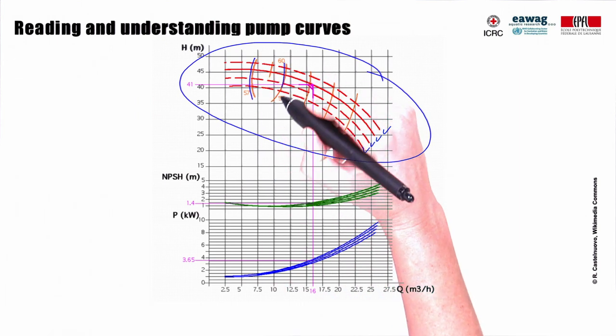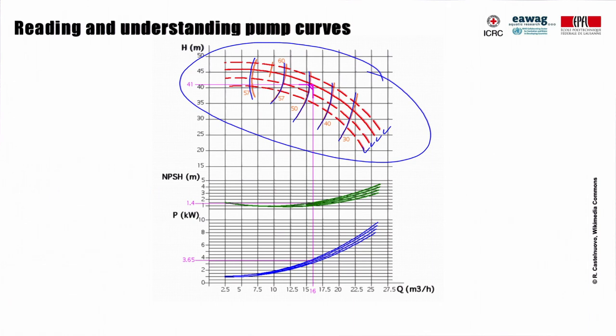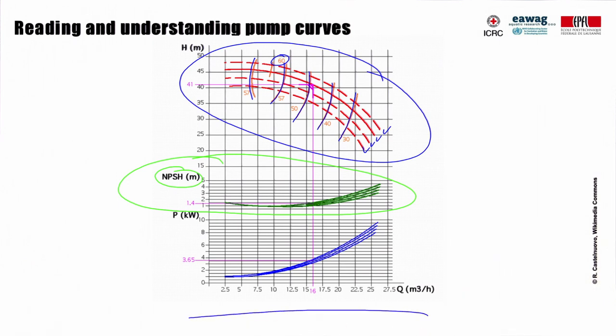In addition to head and flow, pump curves will also provide efficiency information. Efficiency is the relationship between the input power and the water power being generated by the pump. No pump has 100% efficiency and pumps require more input power than water power generated. The best efficiency point on this example is 60%. The middle part of the pump curve illustrates the net positive suction head required, which is basically the suction characteristics of the pump at different flows. Each point along the curve shows the positive suction head in meters required to avoid cavitation, which can damage the pump. As you can see, it does not differ a lot for different impeller trims. The lowest graph at the bottom of the pump curve shows the power curve, indicating how much power the pump will require at any particular flow point. This information is useful for calculating power consumption costs and ensuring that the selected motor is suitable for the chosen pump.